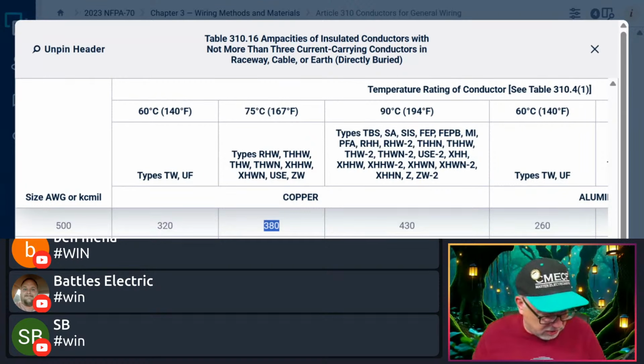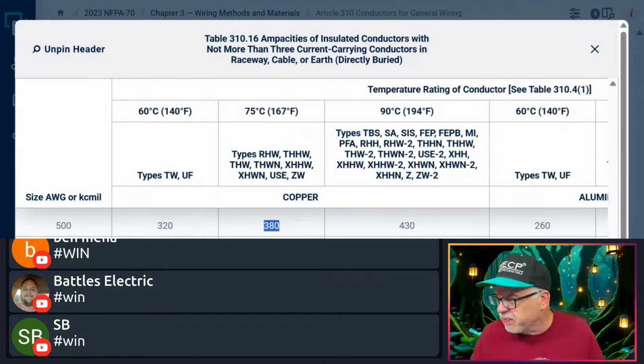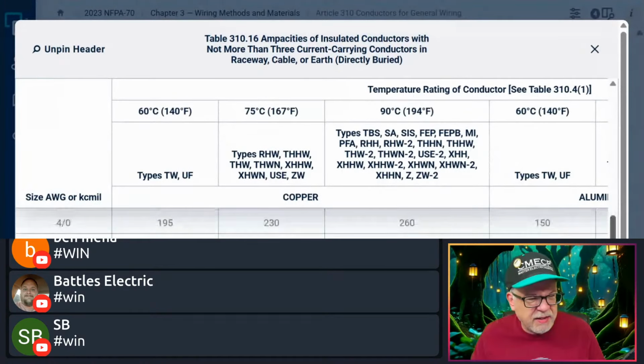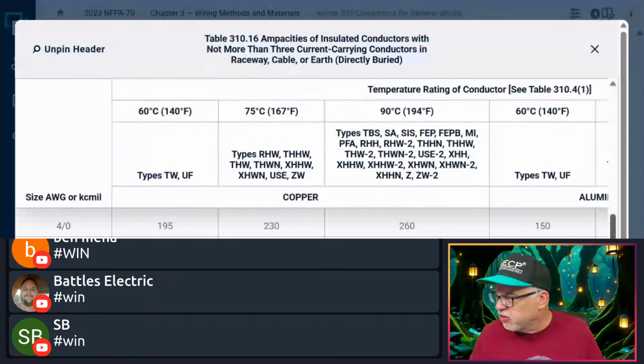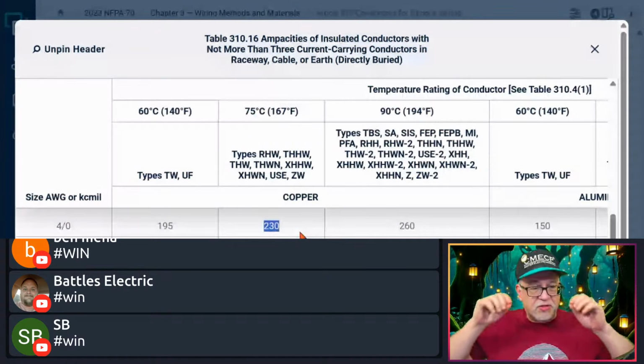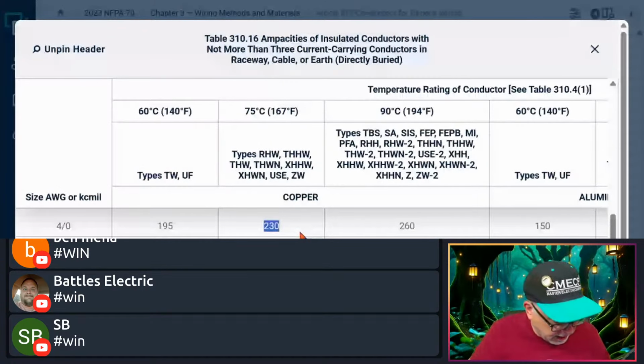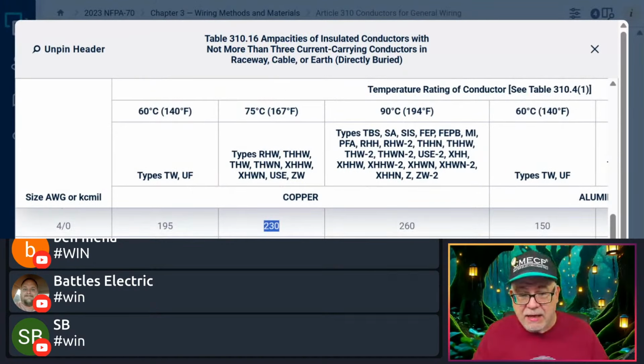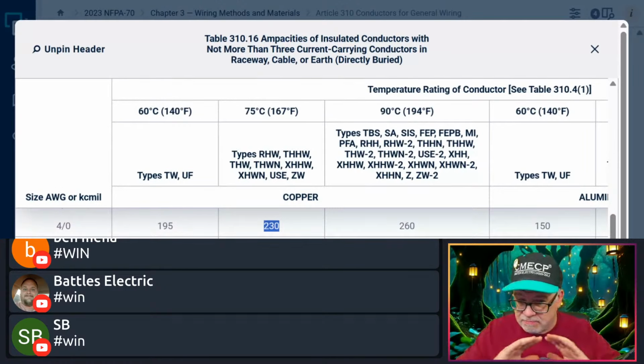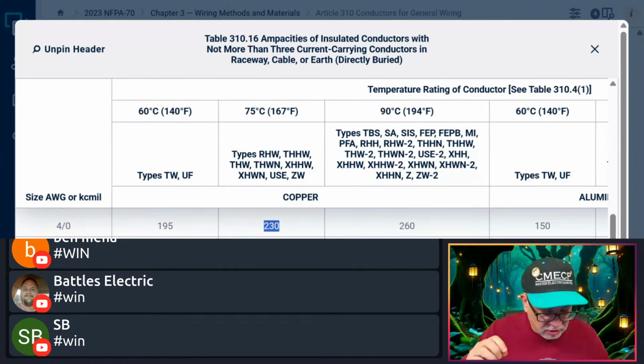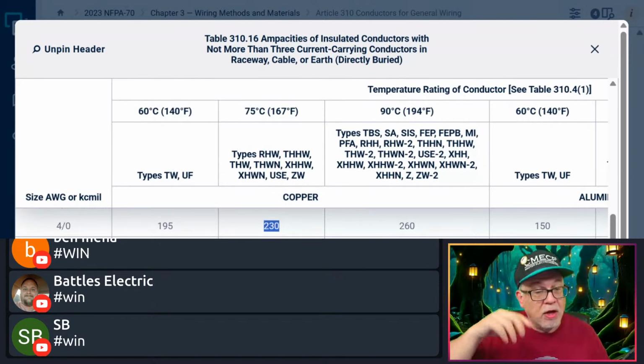Right, the next one was 6 sets of 4-aught. Okay, so let's see what 4-aught's rated at. All right, let's see if I can get it on here for you guys. Right there. Okay, there's 4-aught. 4-aught is rated 230 under the 75, right here. So 6 sets was an option. I'm doing 230 times 6, which is 1380. Is 1380 enough to handle 1200? Yes, it is, right out the gate. So right now it looks like 6 sets of 4-aught, of our options, is winning.